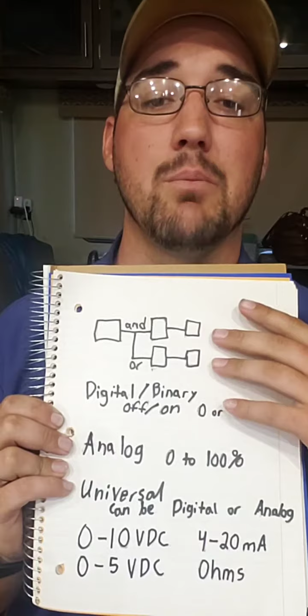If you don't know a thermistor, we all deal with them every day at this point in the trade. They're common items. They just vary in resistance depending on temperature. They are temperature sensitive, so depending on what the temperature is around the thermistor or whatever it's coming in contact with, the logic in the controller knows that that resistance equals this temperature. And sometimes we do have to calibrate that. There are a number of things we have to do, but that is what analog means.